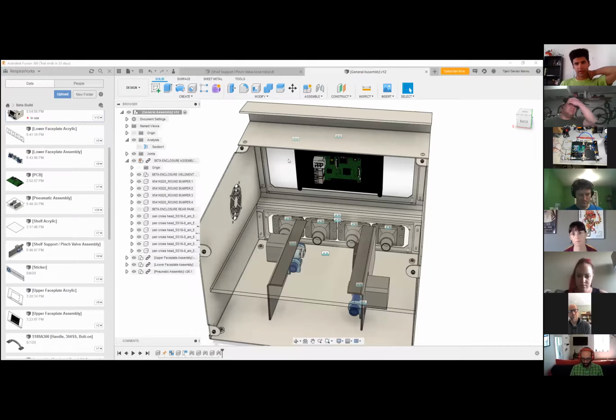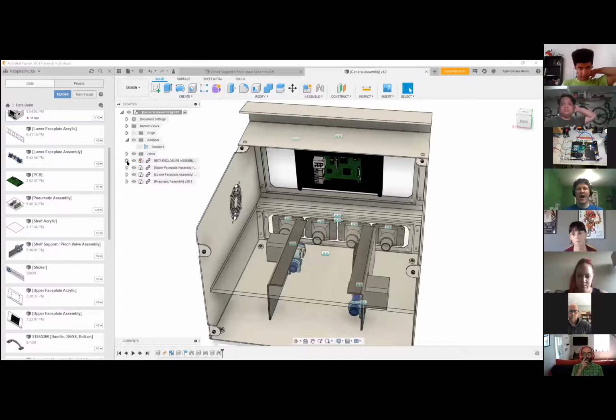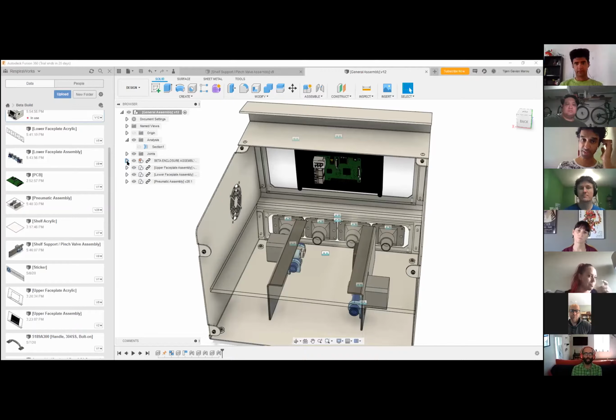Do you think that simply restraining it the way we were talking about wouldn't pass that? I'm just trying to gauge how vigorous these tests are. The tests I'm looking at have peak accelerations from 15 to 30 Gs for shocks on each axis. 30 Gs. And where are these specifications? 80601 212. Wow. There's a shock test. It's like 15 to 30 Gs for like 12 or 6 milliseconds.